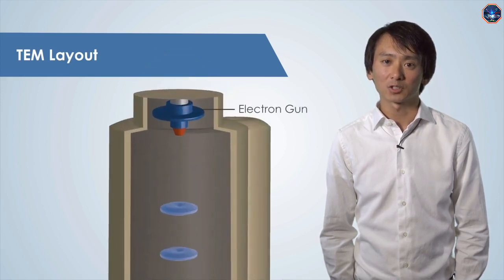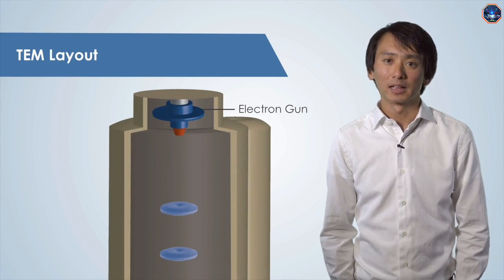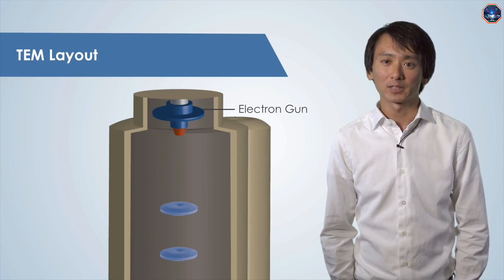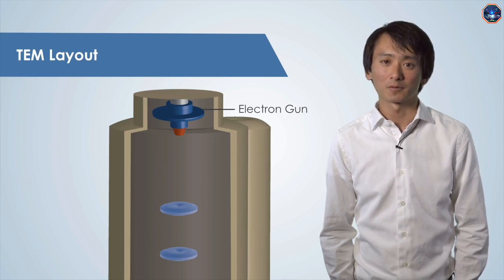With thermionic emission, the electron gun works similarly to an incandescent light bulb. A filament, the cathode, is the source of electrons. It is usually a hairpin-shaped tungsten wire or LaB6 crystal. The filament is heated to a very high temperature and electrons boil off from its tip.